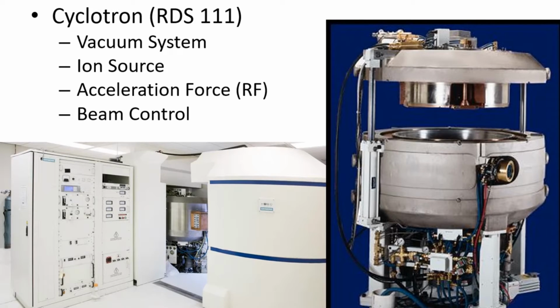We're going to have the beam control to make this a cyclic force and to control our beam to hit a certain window and a certain type of compound that we have in there, whether the target is water or some sort of nitrogen or oxygen gas. Then we can make different radionuclides from that. So our cyclotron pulls, I wrote it down, a vacuum of approximately 1 × 10⁻⁸ torr.